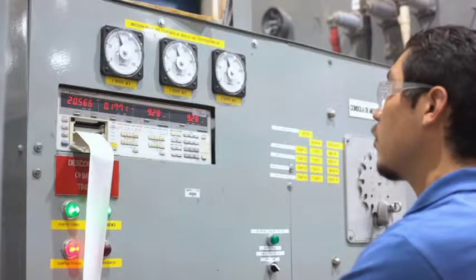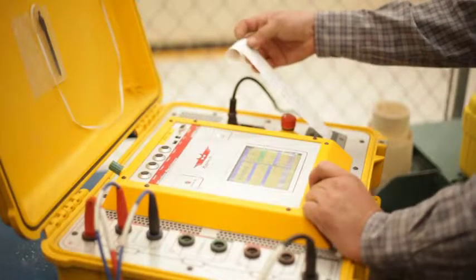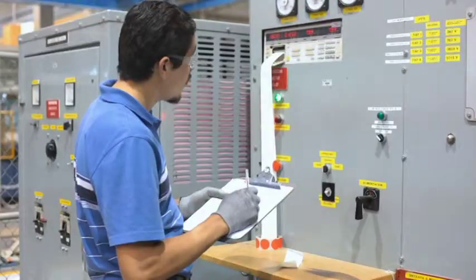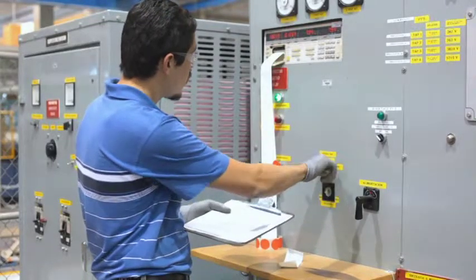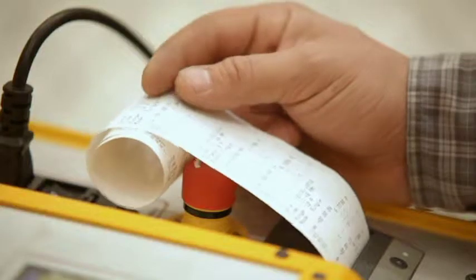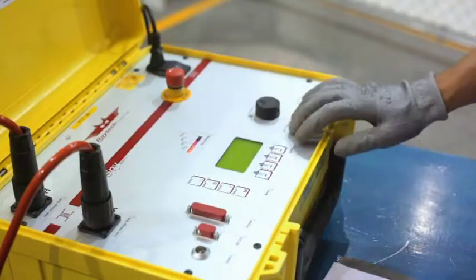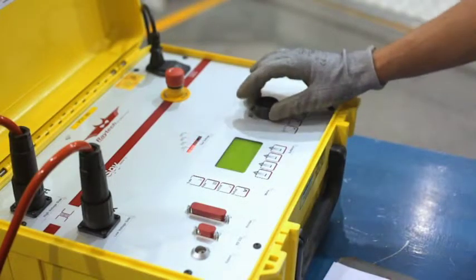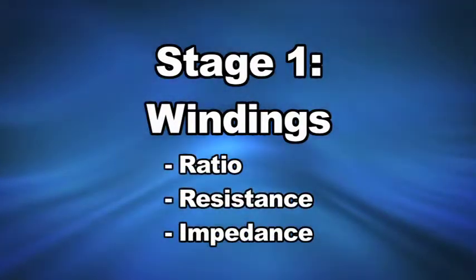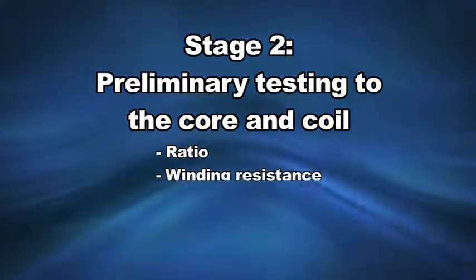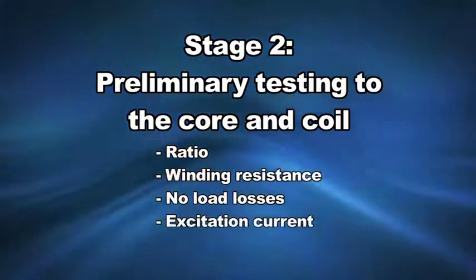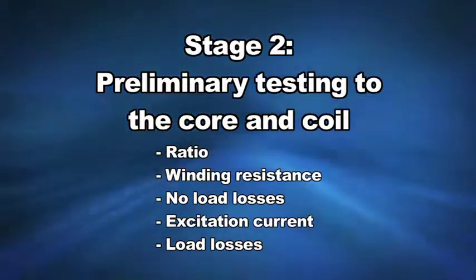Also, in our testing area, we use the test equipment and most advanced technological developments for the appropriate protection, control, and test application. To ensure that each element of the transformer meets the technical and quality requirements, it has a 3-stage protocol of tests as follows. To windings: ratio, resistance, and impedance. Preliminary testing to the core and coil: ratio, winding resistance, no load losses, excitation current, and load losses. Final transformer test.